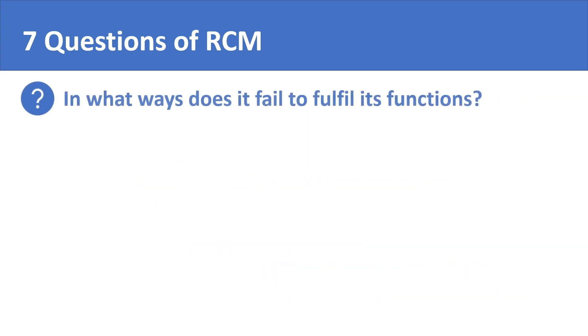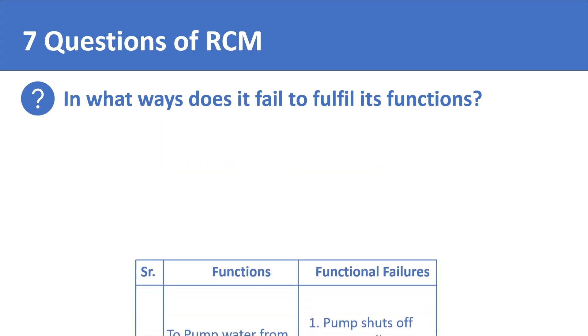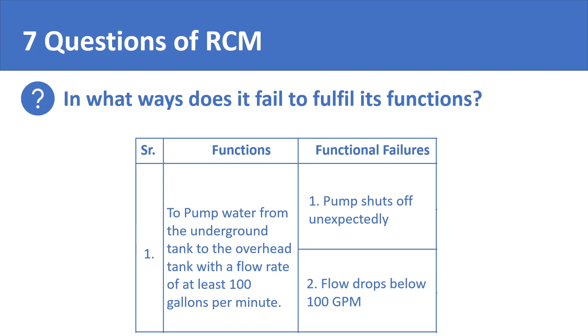The second question is: in what ways does the equipment fail to fulfill its functions? The ways in which a piece of equipment could fail are known as functional failures. For example, the pump could fail in performing its function if it trips or if the flow rate drops below 100 gallons per minute. So the second RCM step is to work out the different types of functional failures that your plant equipment could experience.